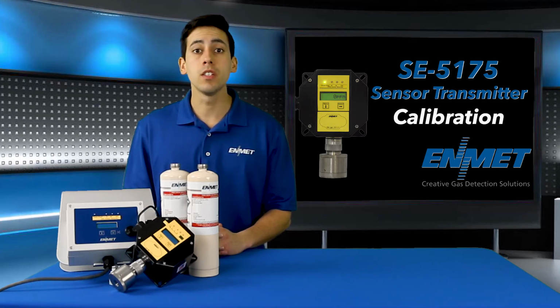ENMET recommends at least a quarterly calibration of the SE-5175 instrument. You can follow these steps to calibrate any of the SE-5175 sensor transmitters. The only difference will be the span gas in use. The SE-5175 I will be calibrating is set up for 0 to 500 ppm range, and I will be using 100 ppm CO to calibrate the instrument.